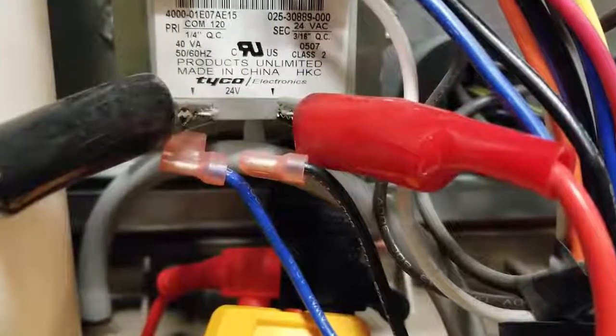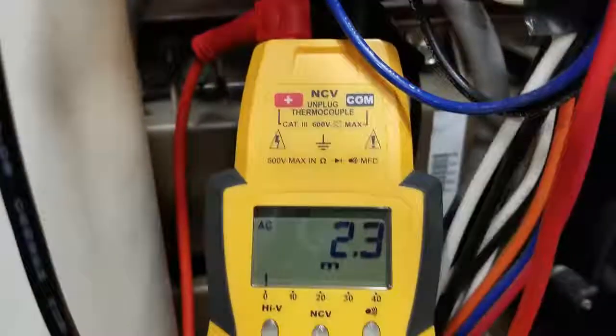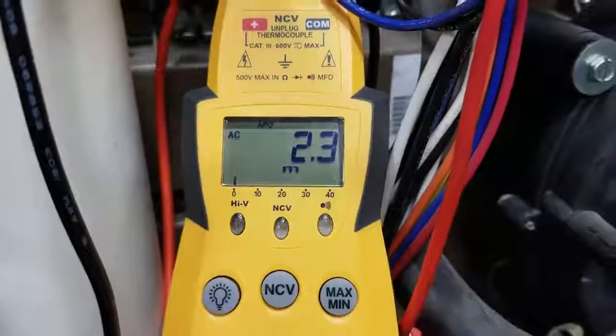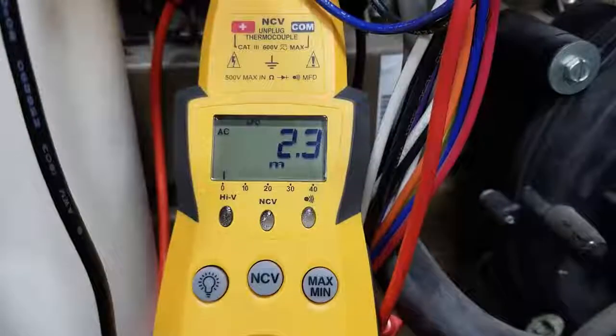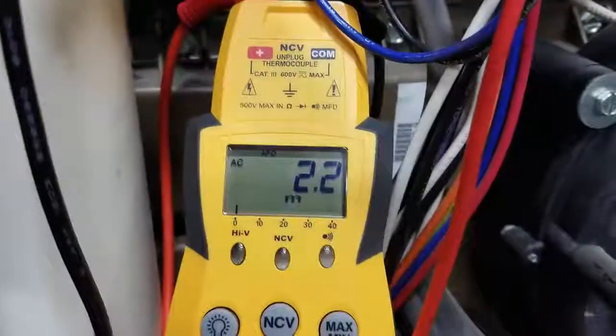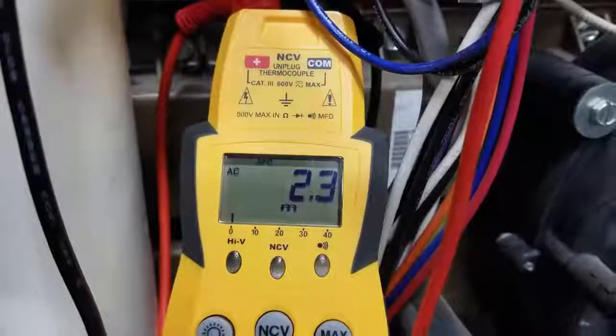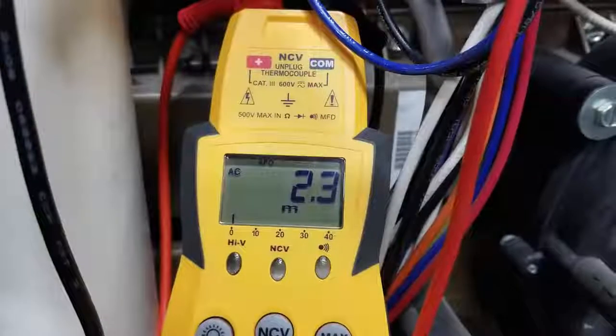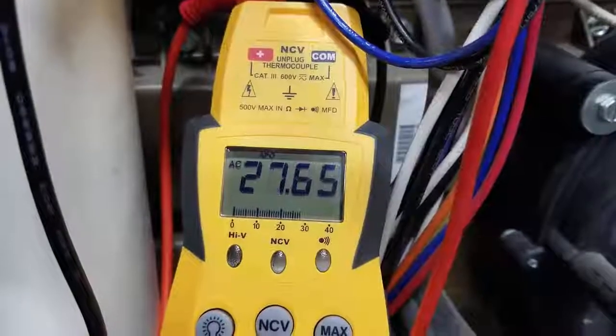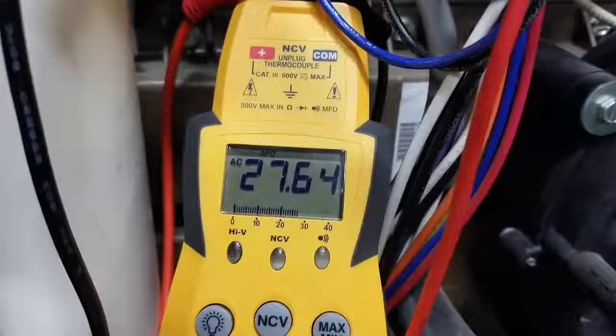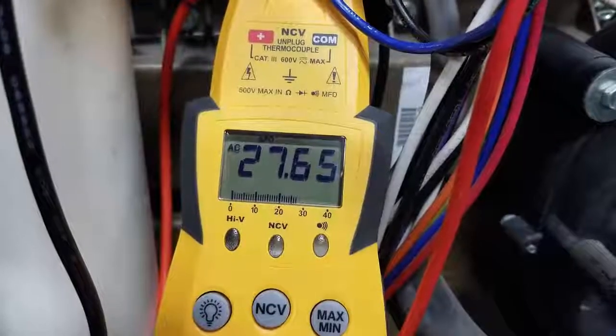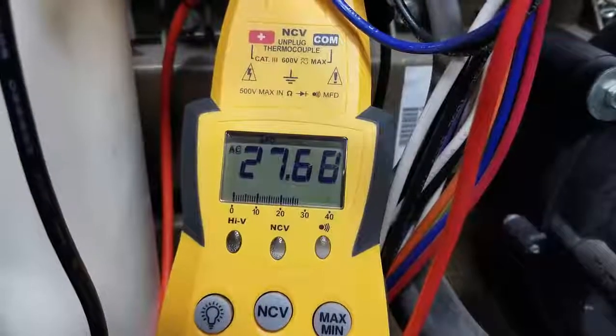Okay, now I've connected my voltmeter to the secondary or low voltage side of the transformer. Just took the wires off. I currently have the power turned off to the furnace, so we shouldn't be reading any voltage. What you're seeing there is just millivolts, just residual stuff in the system. I'm going to go ahead and flip the power back on. If we have correct voltage to the transformer and the transformer is good, we should see 24 volts plus or minus 3 or 4 volts. So now we know we have a good transformer in this furnace.